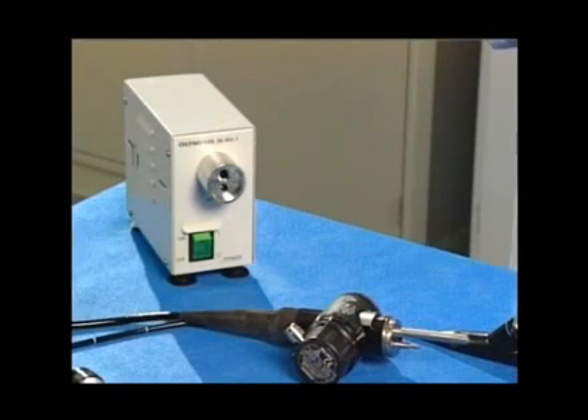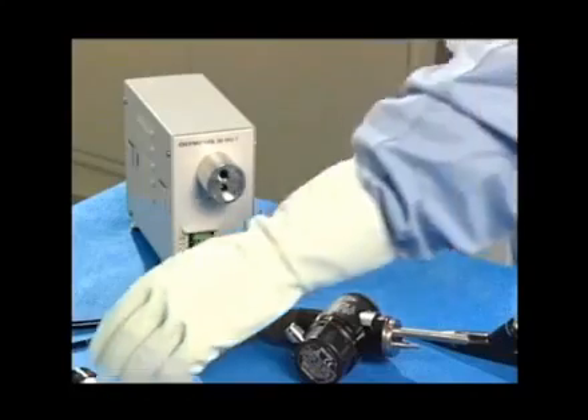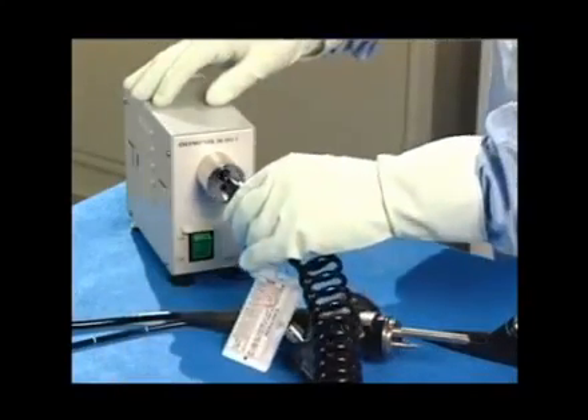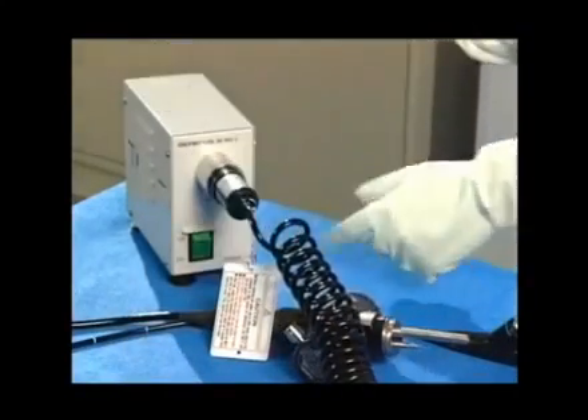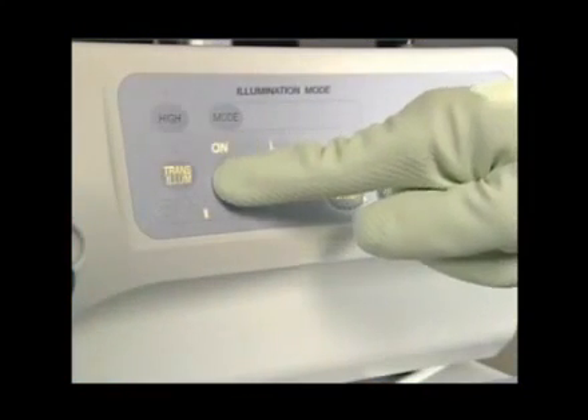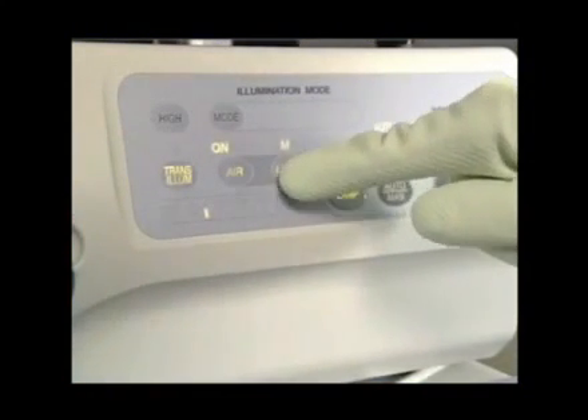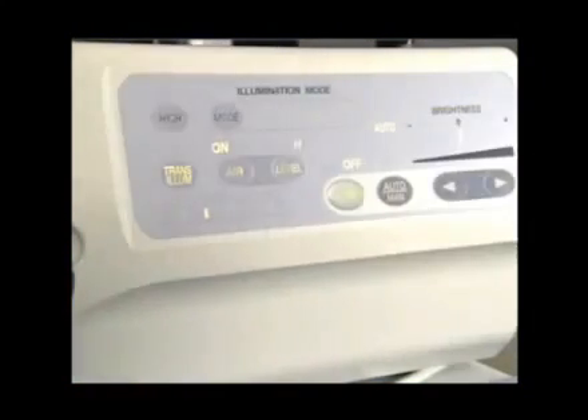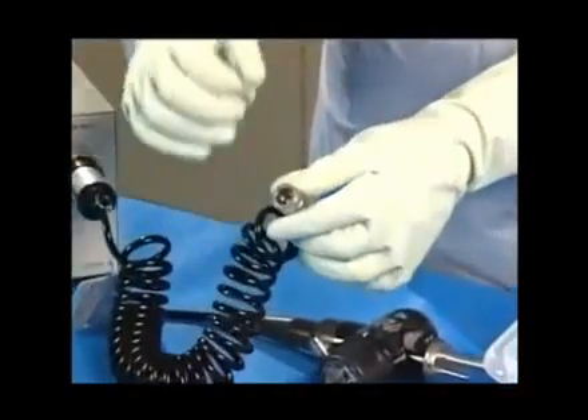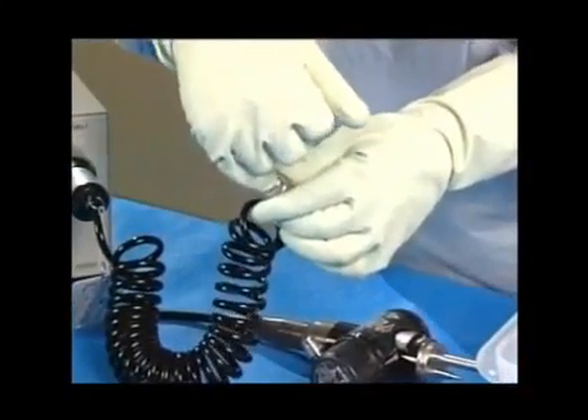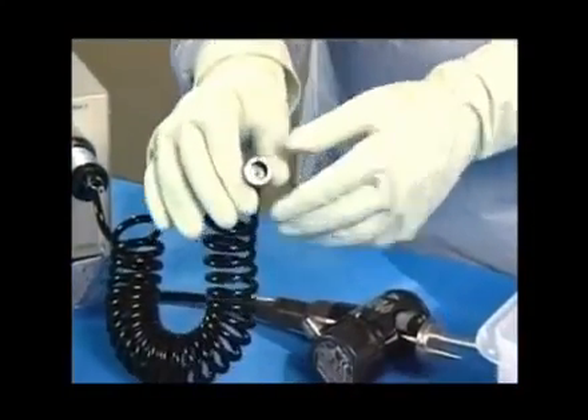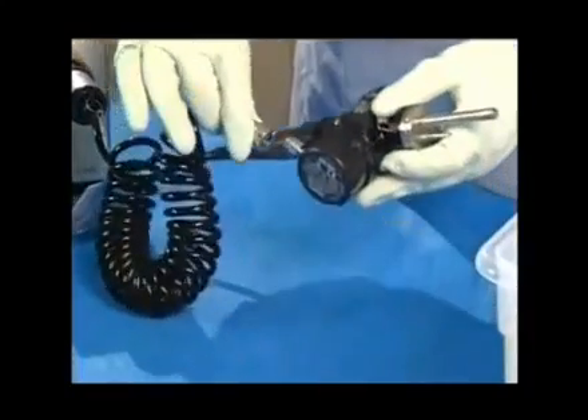Attach the leakage tester to the MU1 maintenance unit or to an Olympus light source. Turn on the air supply. If you are using a light source, be sure to set the airflow rate to its maximum setting. Depress the pin inside the connector and confirm that air comes out of the cap.